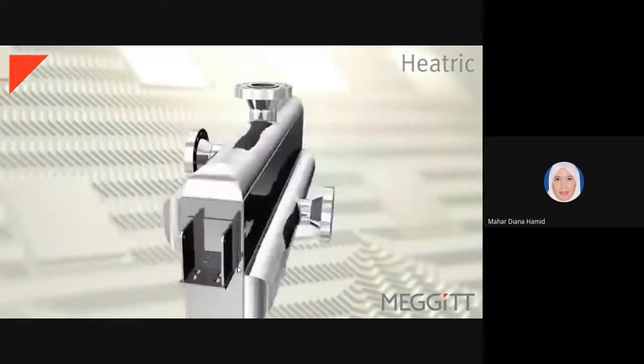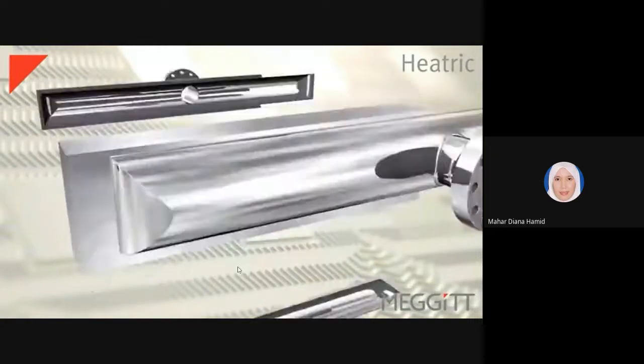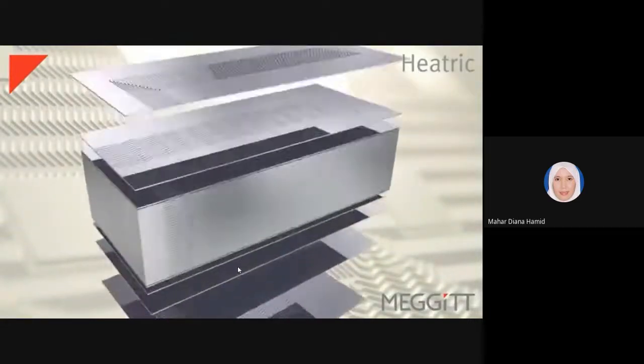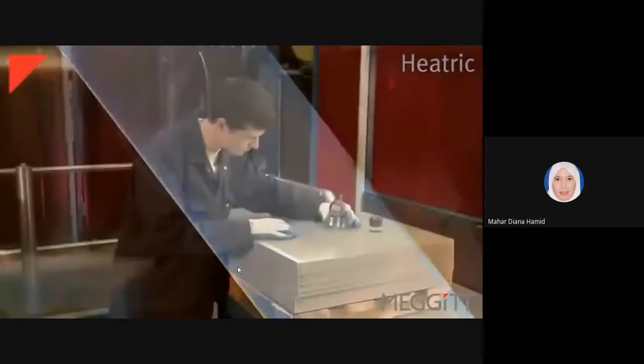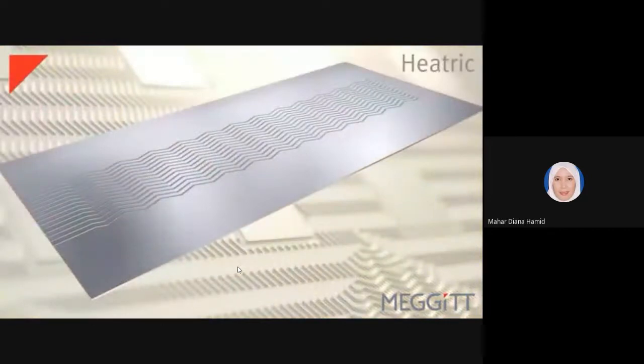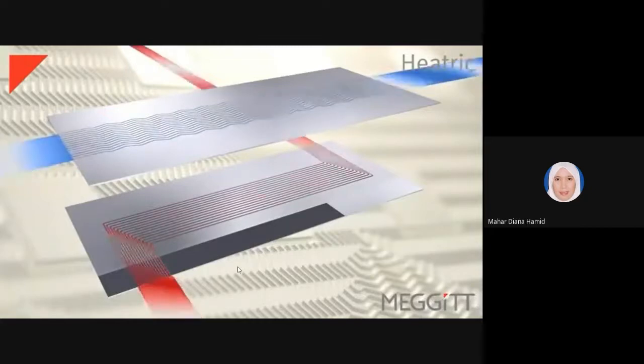Now, let's look at the construction of the heat exchanger. A heat exchanger is constructed from flat metal plates into which fluid flow channels are chemically etched. These fluid flow channels are typically 2 millimeters wide and 1 millimeter deep semicircles. The plate layout and flow patterns for the cold and hot sides of the exchanger are designed to suit the particular duty. Each exchanger is uniquely designed to offer an optimized balance between heat transfer, pressure drop, thermal effectiveness, and mechanical requirements.